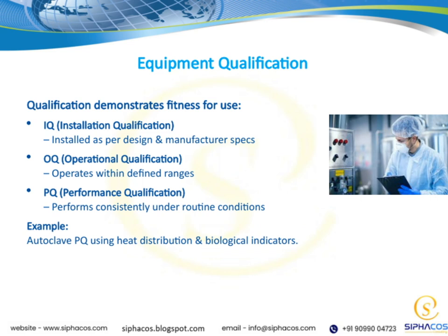Then we have PQ, or performance qualification. This is where we verify that the equipment performs consistently over time under routine conditions. It's about ensuring reliability and ongoing performance. For example, when qualifying an autoclave during its PQ, we would use heat distribution and biological indicators to confirm it sterilizes effectively and consistently.